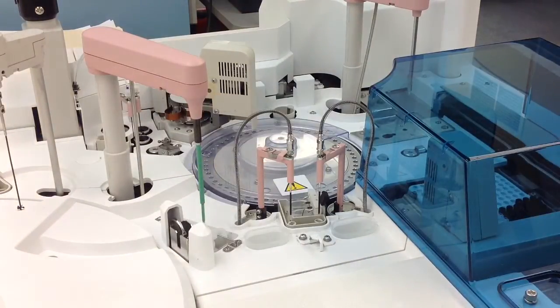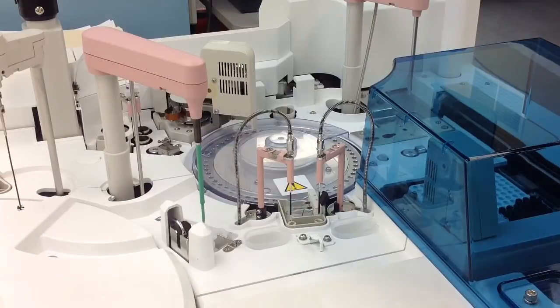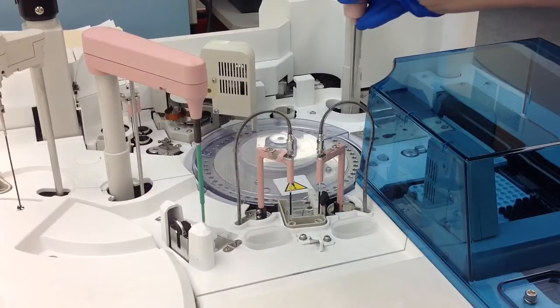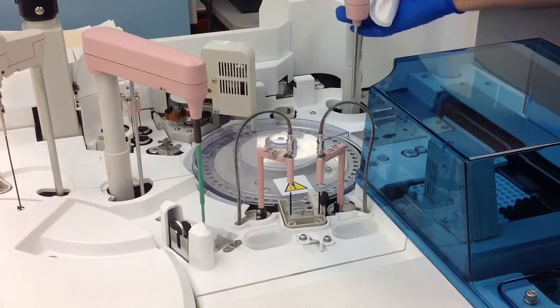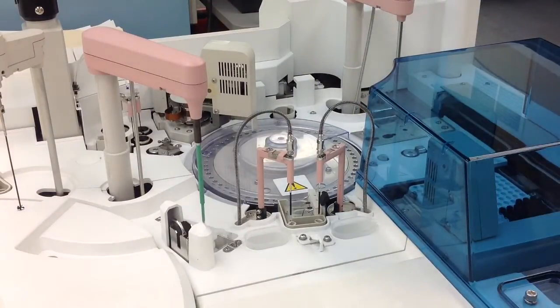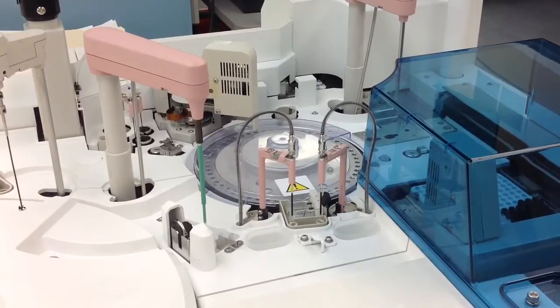Now when it comes to the sample probe in the back right corner, that one right there, you actually just use the lint-free gauze and deionized water. You don't use alcohol for this one and that's all there is to it. Thanks for watching.